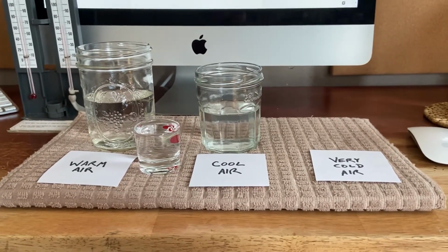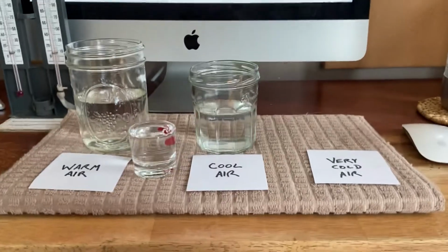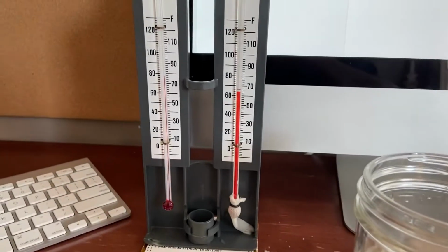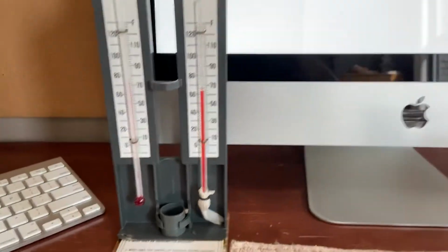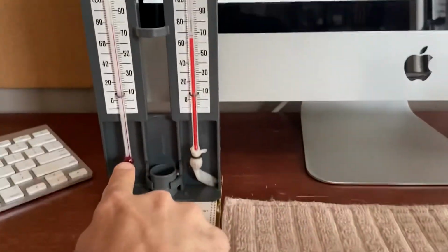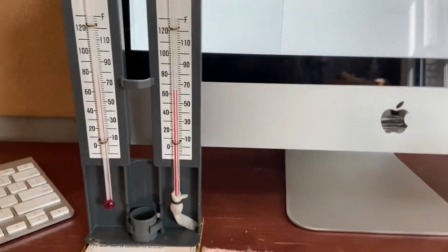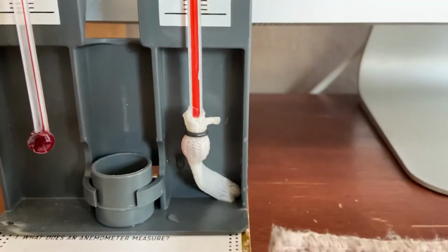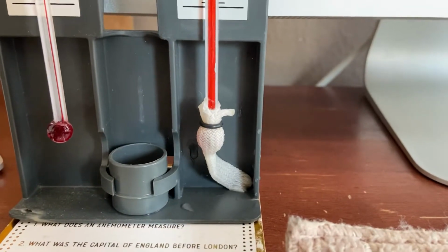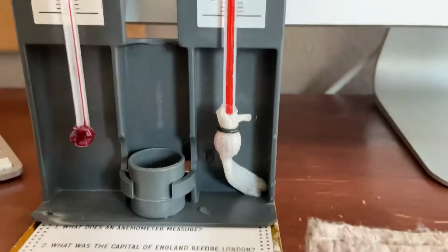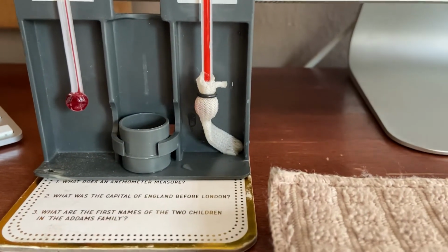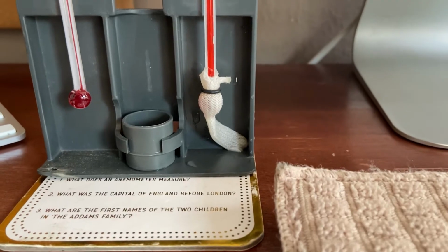Okay, now how do we determine relative humidity? We determine relative humidity by using an instrument called a psychrometer. Okay, so this is how it works. We've got 2 thermometers. One is dry, and one actually has a wet cloth around it. So what's going on with the wet cloth is this. Since water is evaporating, and we know it takes energy to evaporate water, the water is taking energy away from this thermometer, and the temperature should be lower.